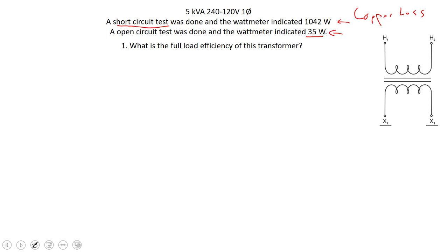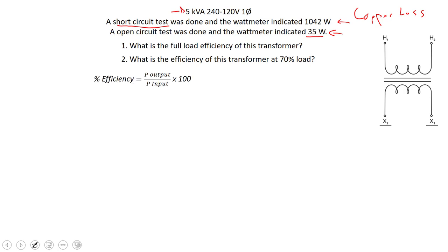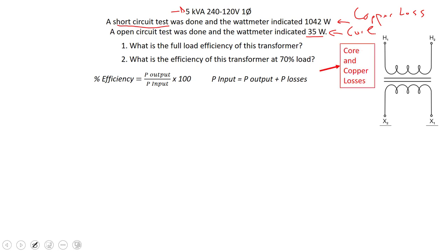What we're going to try calculating here is the full load efficiency of this transformer — loading it up to the full 5kVA. Then we'll redo this at 70% of that load. The efficiency formula is: percent efficiency equals power output divided by power input, and power input is power output plus losses. We've got two types of losses: core losses and copper losses. The short circuit test gives us copper losses; the open circuit test gives us core losses.